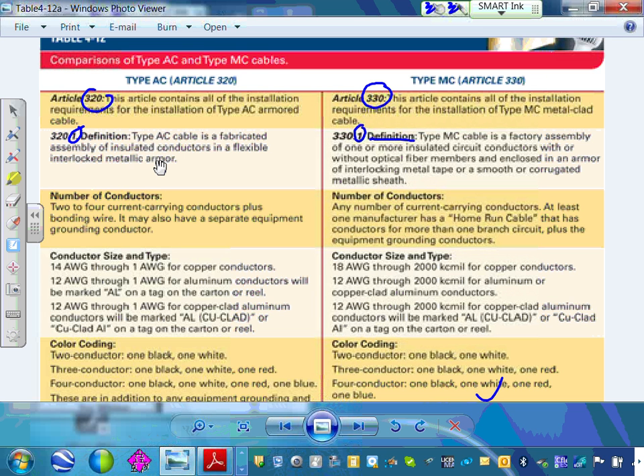Okay, so that's the definition. Number of conductors - look at this guy. It can have 2 up to 4 current-carrying conductors with a ground. Any number of conductors - can you see the superiority? I'll remind you, this one is more superior than that one, since it allows any number of current-carrying conductors. So can I get MC cable with 6 current-carrying conductors in a cable? Yes. That other guy is limited to 2 or 4. So if you're doing industrial or commercial work and need 6 or 4 circuits in a cable, you'd use MC cable - you see the limitation of using the other one.